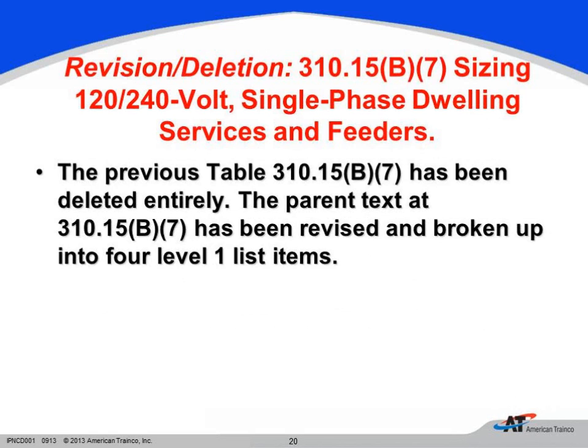This is a major change for the people that do residential, because in 2011 we had a table that once we calculated the load for the service for a single-family dwelling, we could go to that table and we had our choices. It could be 100 amp, 125, 150, 175, 200, and that table went all the way up to 400 amps. Well, that table has been deleted completely now. So that table is gone, and what they have given us in Annex D is an example of how to calculate our load now for a single-family dwelling.